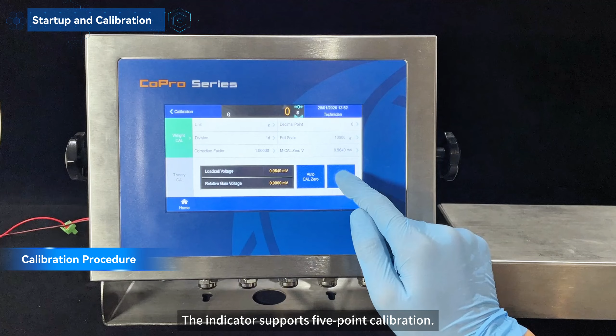Set the unit, decimal point, division value, and capacity according to the actual application requirements. Tap Auto Zero to complete zero calibration. Proceed with gain calibration by tapping weight calibration. The indicator supports 5-point calibration, though in this video only calibration point 1 is demonstrated.